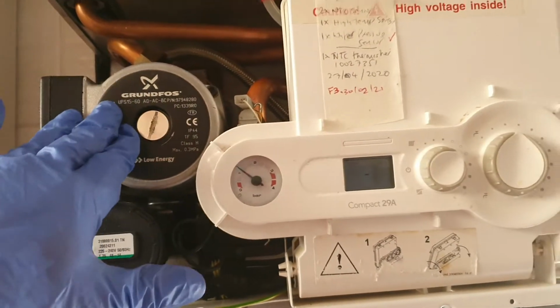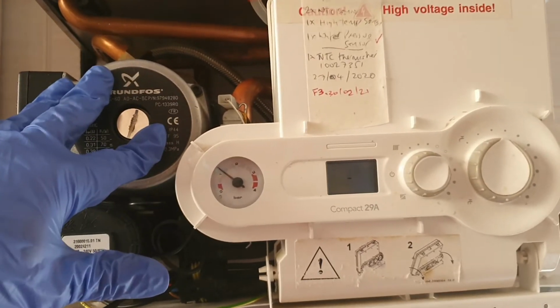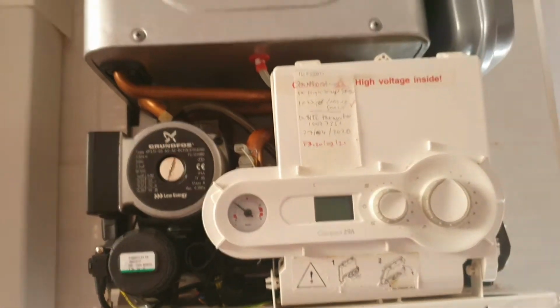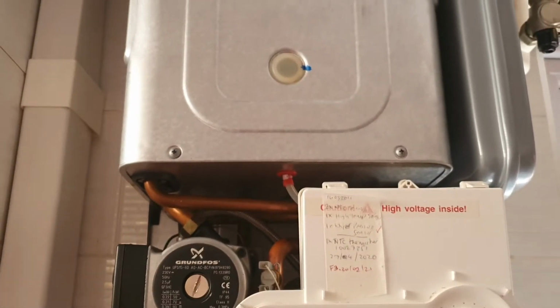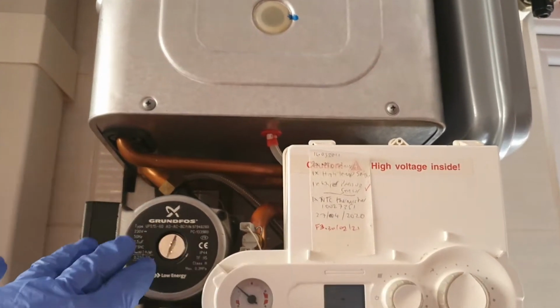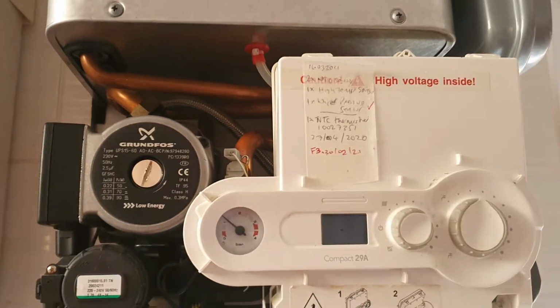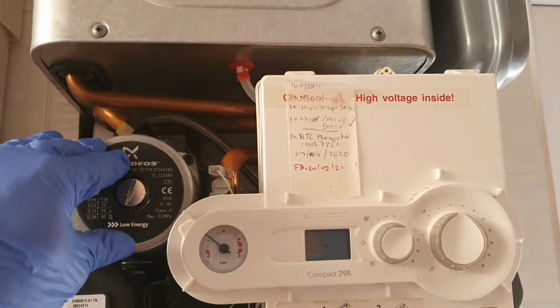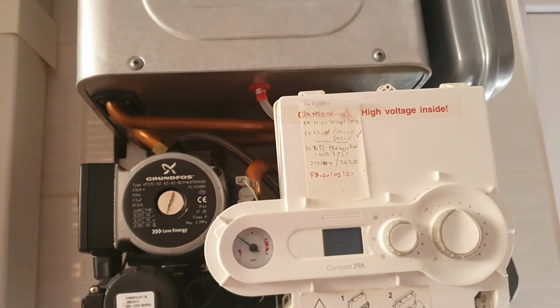But you can't hear it as bad nearby. There was a bit of a dilemma that it could have been the fan, extractor fan, or the fan for the flue, or fume fan, whatever you want to call it. But it's not that, because the way to determine that is to go outside, turn the boiler on, leave it running.